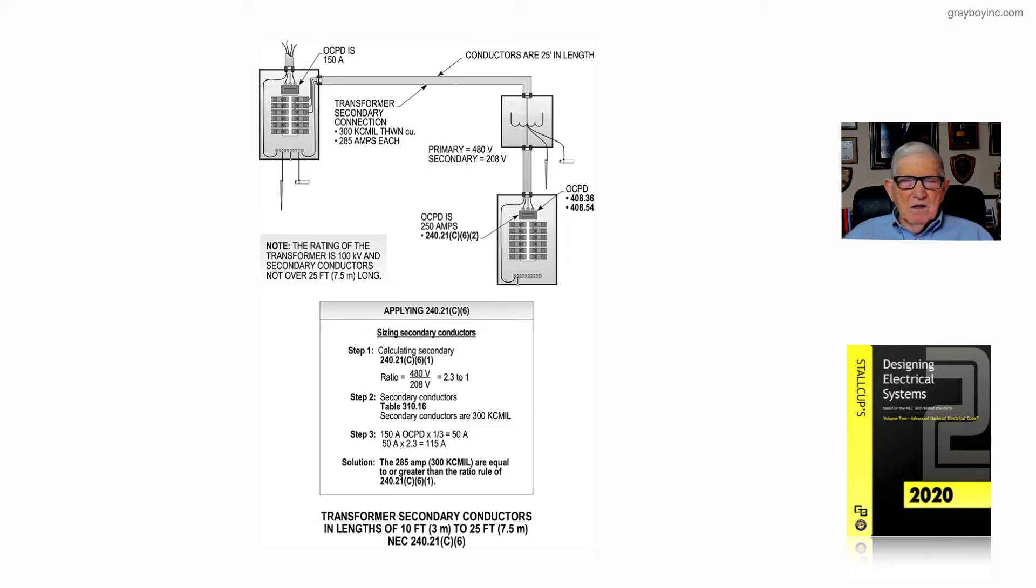Now, let's just take a look at the procedure for calculating the appropriate size conductors and overcurrent device and so forth to meet 240.21C6. So let's look at applying 240.21C6 in the other boxed-in information. And notice in step one, you have 240.21C6 item one.